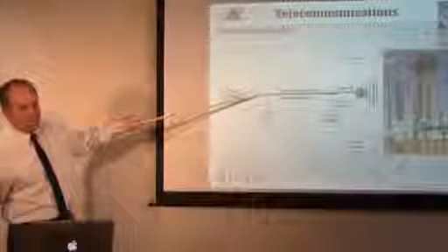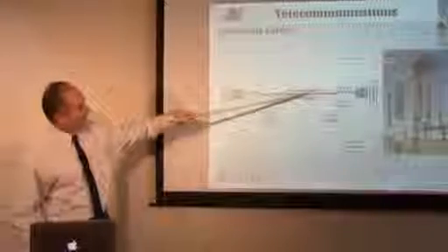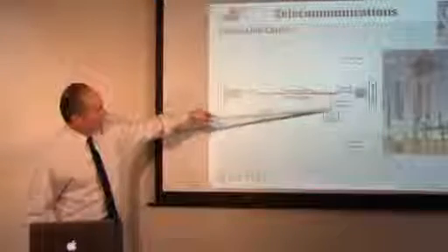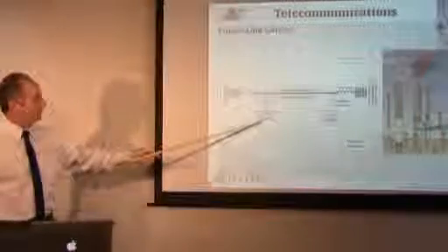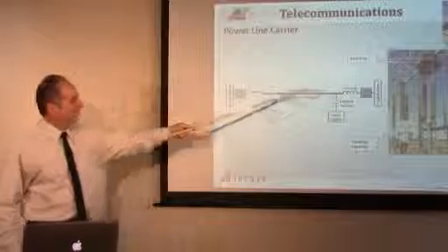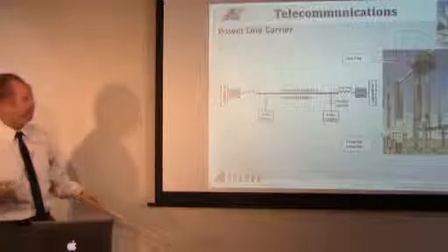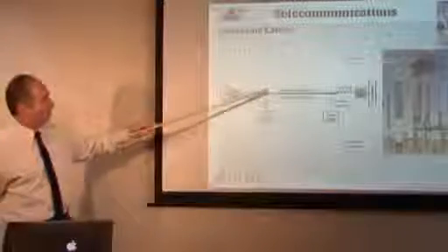So your radio frequency energy goes through the capacitor, is blocked by the coil, travels down, propagates down the transmission line, blocked by the line trap at the other end, and goes into the radio at the far end. So we have radio high frequency communications on power line carrier, usually one conductor of the three-phase line, typically the center conductor, and we have line traps.